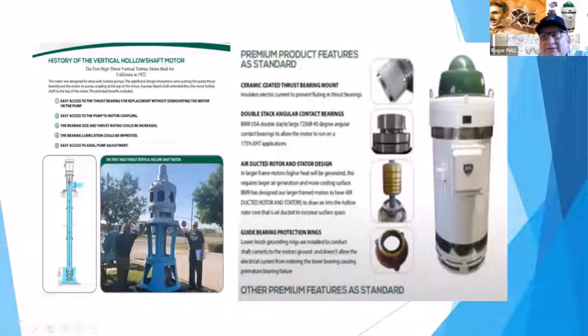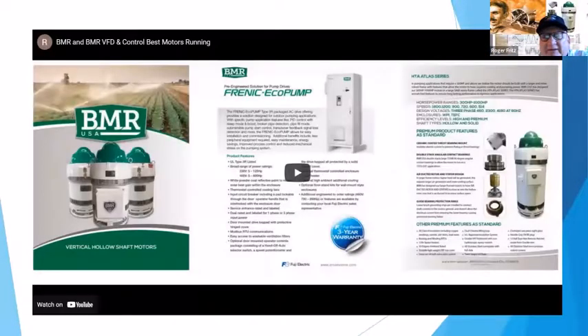They put insulators in here because of those frequencies, and they also put grounding rings on them. When you get above about 100 horsepower and you put a VFD on it, you'll create more static noise, and that static then wants to run through the bearings, and you'll have bearing failures over time. So it's just important to know that stuff's out there.